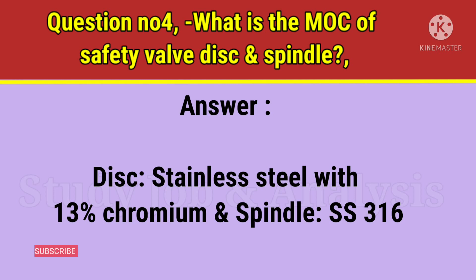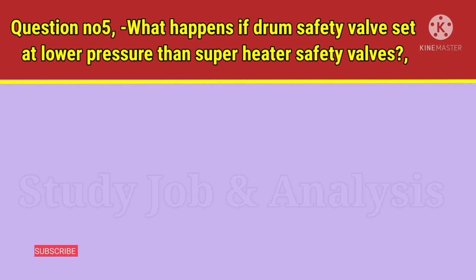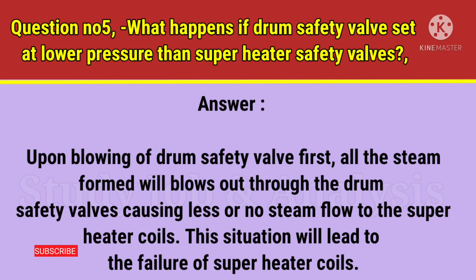Question number 5: What happens if drum safety valves are set at lower pressure than superheater safety valves? Answer: Upon blowing of the drum safety valve first, all the steam formed will blow out through the drum safety valves, causing lesser steam flow to the superheater coils. This situation will lead to failure of the superheater coils.